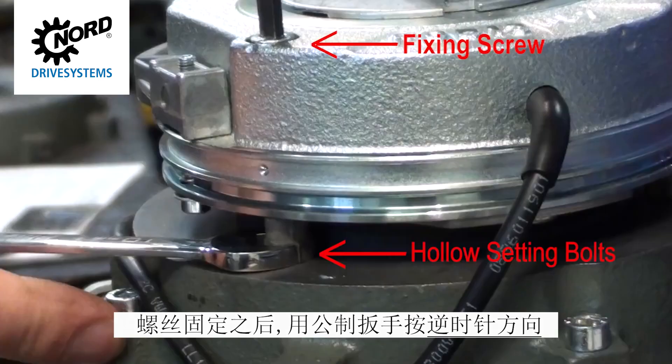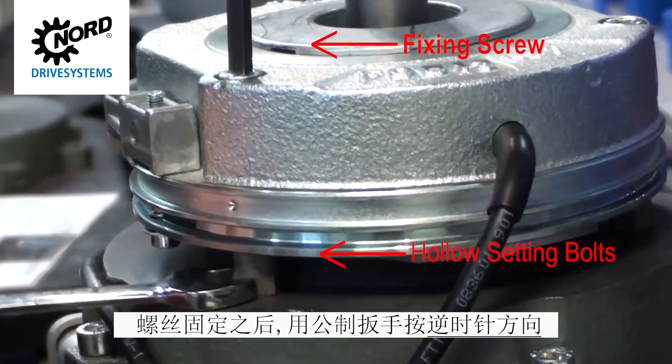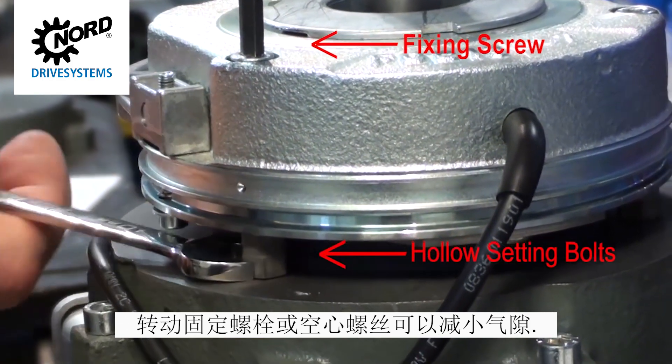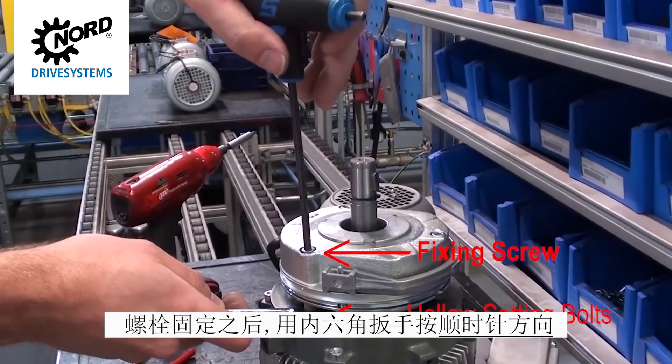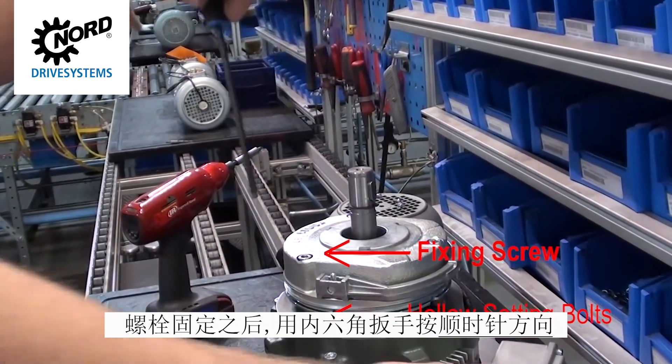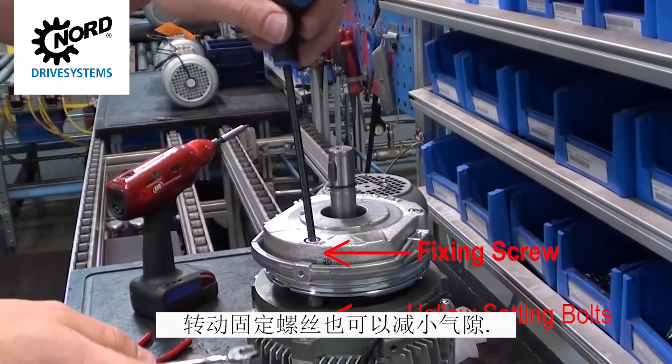Decreasing the air gap is accomplished by using a metric wrench to turn the setting bolts or hollow screws counterclockwise while securing the fixing screws. Decreasing the air gap can also be accomplished by using an Allen key to turn the fixing screws clockwise while securing the setting bolts.